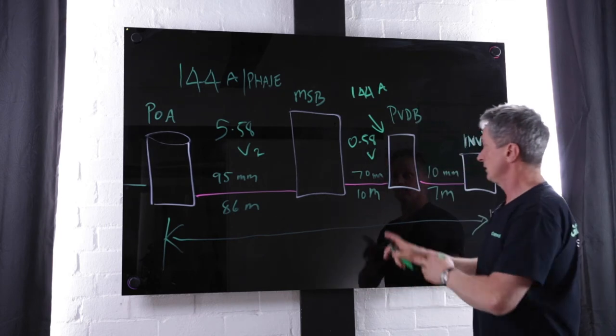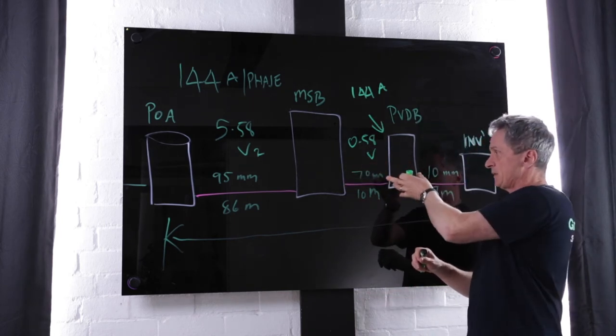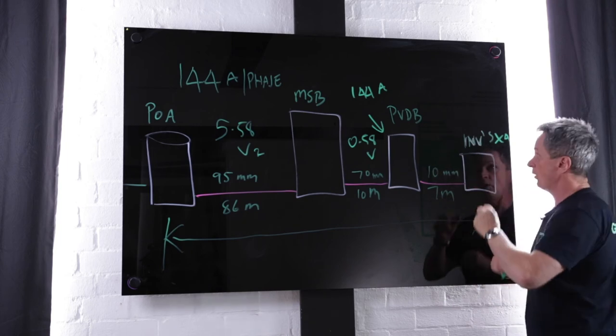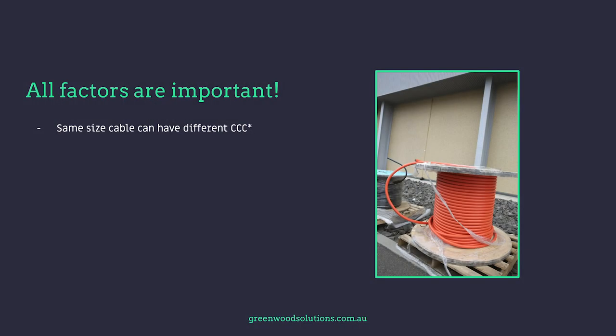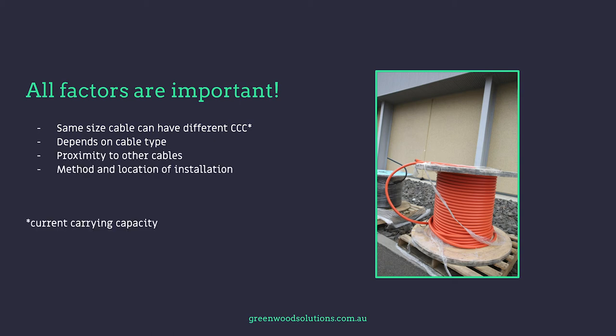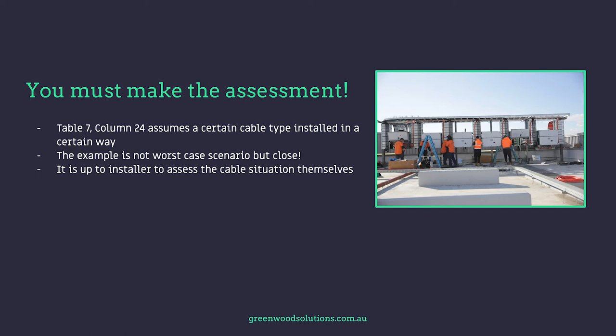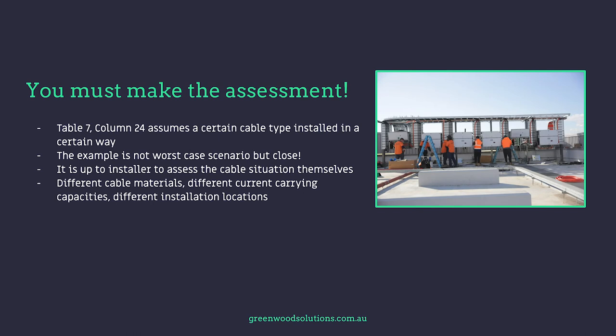Methodically: current carrying capacity of the cable — tick; volt rise — tick; current carrying capacity of cable between the MSB and the PVDB — tick; volt rise — tick; and then the last section where the inverter or inverters connects. The same size cable can have a different current carrying capacity depending on the cable type, proximity to other cables, method and location of installation.